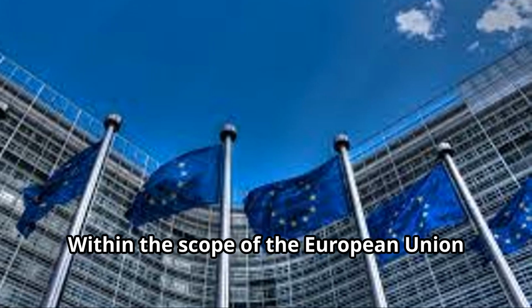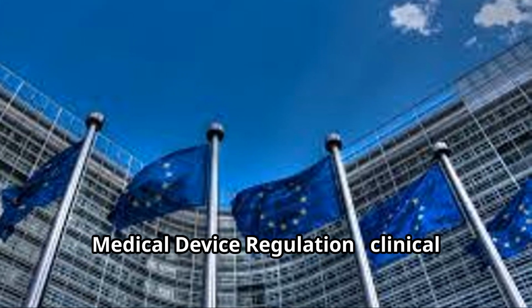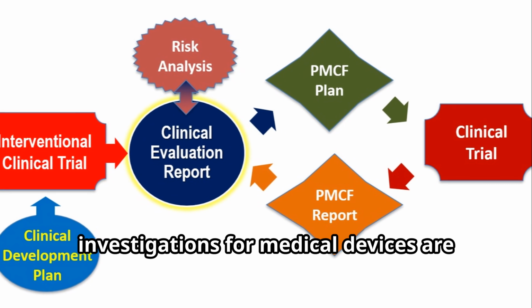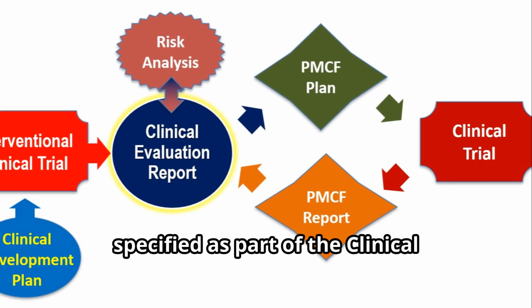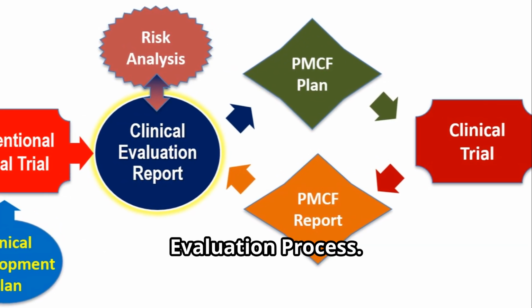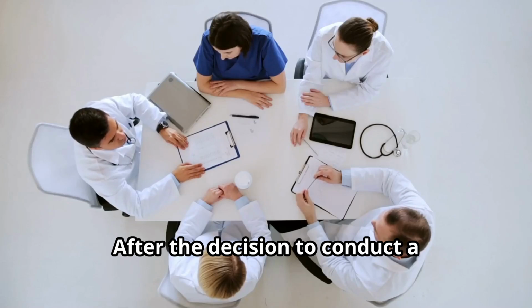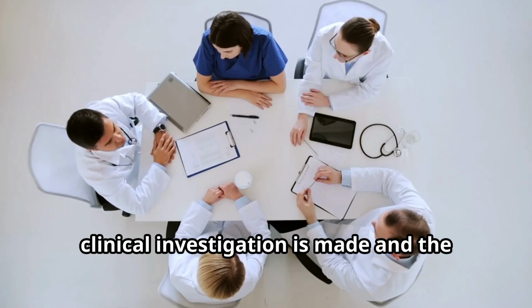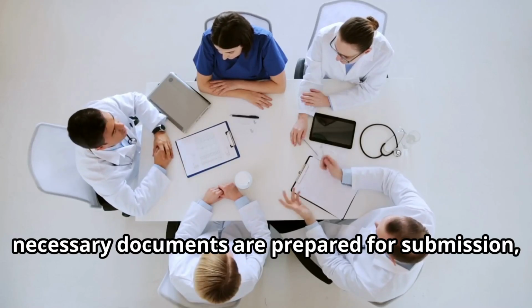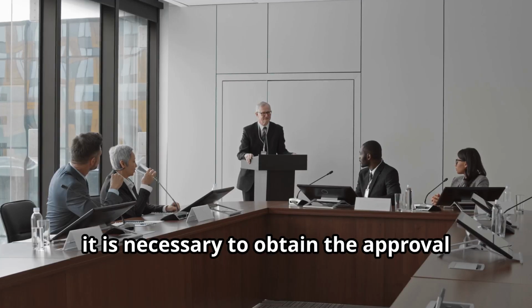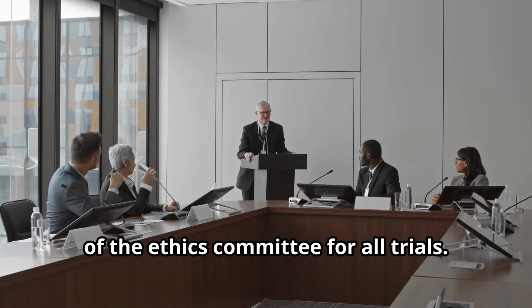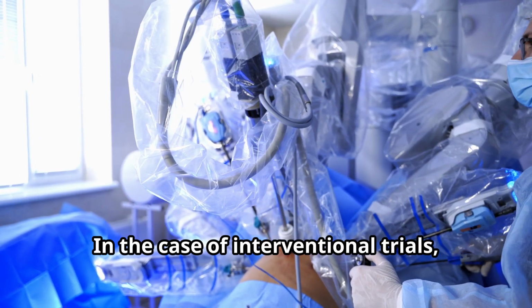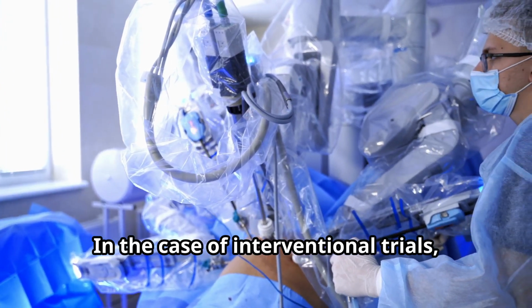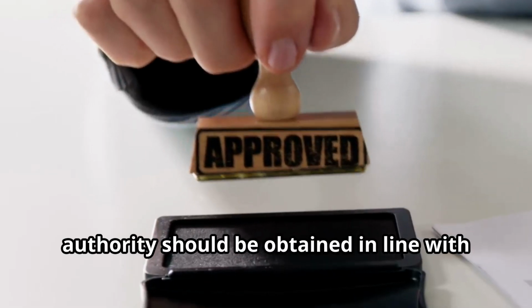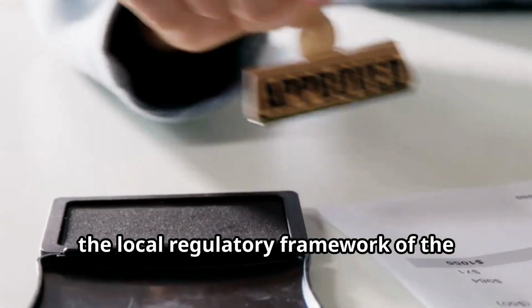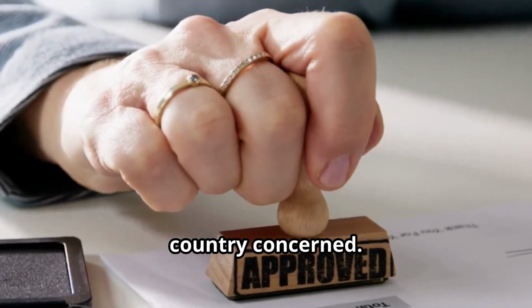Within the scope of the European Union Medical Device Regulation, clinical investigations for medical devices are specified as part of the clinical evaluation process. After the decision to conduct a clinical investigation is made and the necessary documents are prepared for submission, it is necessary to obtain the approval of the Ethics Committee for all trials. In the case of interventional trials, authorization from the competent authority should be obtained in line with the local regulatory framework of the country concerned.